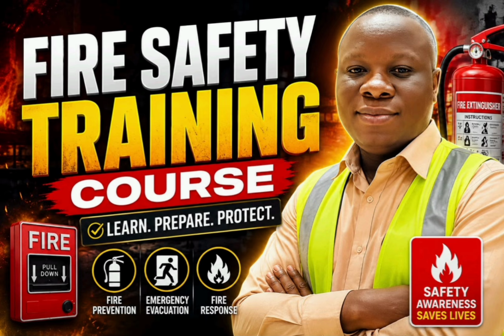Then there is what we call a fire drill. A fire drill is a practical exercise designed to test emergency arrangements. A fire drill can evaluate fire alarm response, evacuation time, employees' awareness, emergency communication, assembly point procedure, head count, coordination between departments, and emergency response weaknesses. After the fire drill, the team should identify lessons learned and corrective actions. After you have conducted a fire drill, what are the identified lessons and what is supposed to be done to improve?